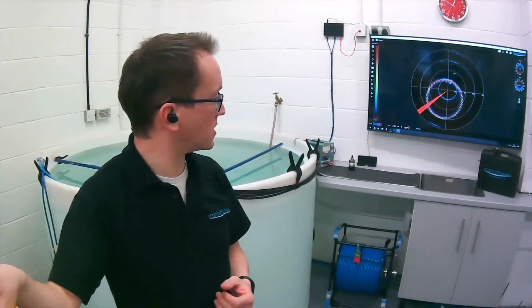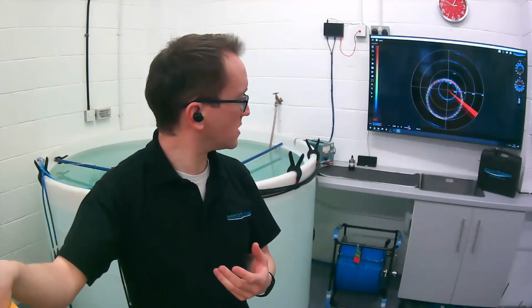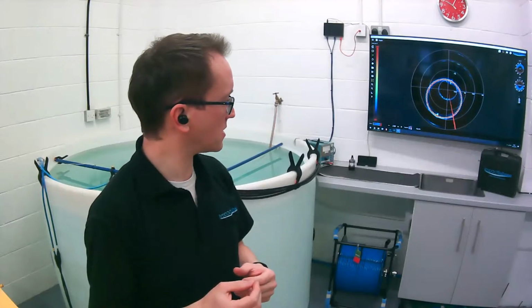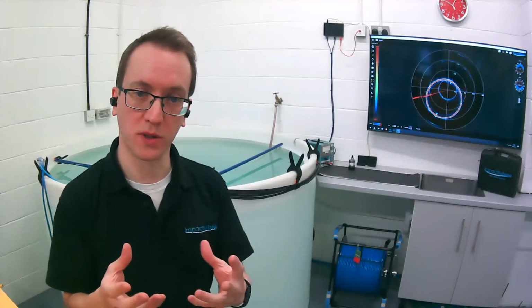I can adjust the scan speed, and there's a little slider bar down at the bottom of the screen, so you can adjust from high speed to high resolution. And as it's set to high speed just now, if I move it up to high resolution, to higher quality, you'll see the sonar slows down, but we start to get a much higher resolution, more accurate image of the tank. And so it's really designed so that if you're using the sonar for obstacle avoidance, you can set it to the fast speed. You just need to know, is there something in front of me, or trying to locate a target around you? Scans around really fast, updates fast.